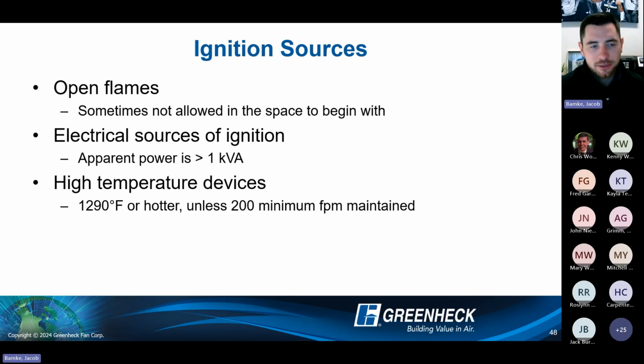So what do we mean by ignition sources? First one is any open flames. Sometimes these are not allowed in the space to begin with, so some codes will lock that out. But assuming we have a leak in the unit on the roof and we go into that sequence, open flames must be put out. And then electrical sources of ignition are based off of an apparent power value. If it's greater than 1 kilovolt ampere, you have to shut down that source of ignition. And anytime you have a high temperature device, that is also classified as something that you must shut down. That's basically 1,290 degrees or hotter, unless you maintain that 200 minimum feet per minute requirement.